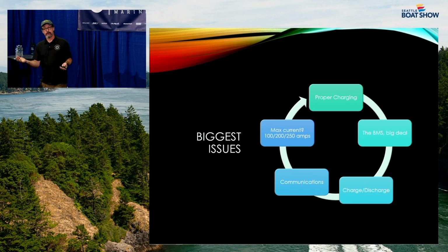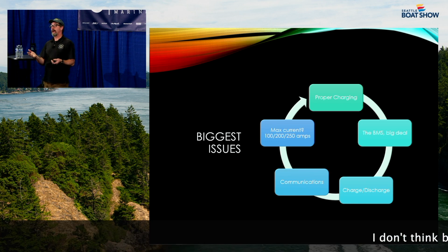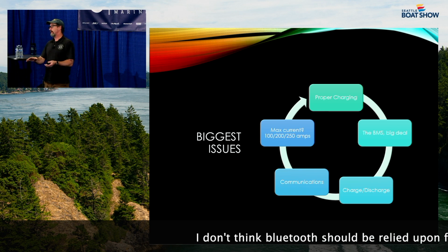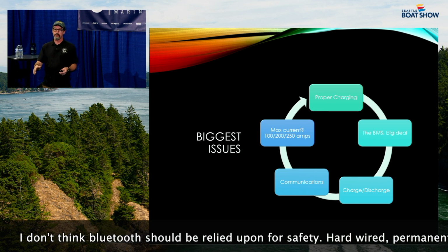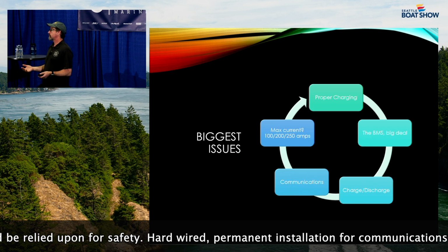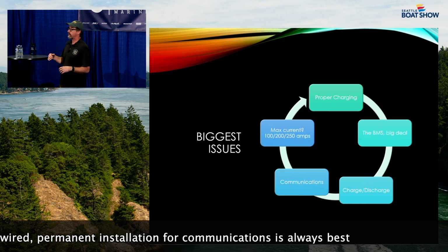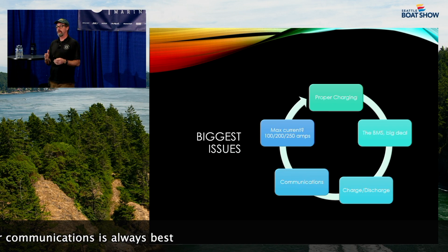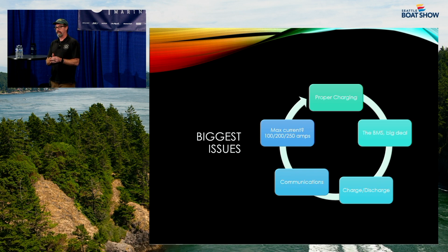Now, the communications piece is key. A lot of the batteries will now tell you you're at 20%, it'll send an alert; you're at 10%, it'll send an alert. Make sure that if you're investing a lot of money in lithium, you have the capability to monitor what percent state of charge the batteries are at, because trust me, you don't want to let them sit around dead.